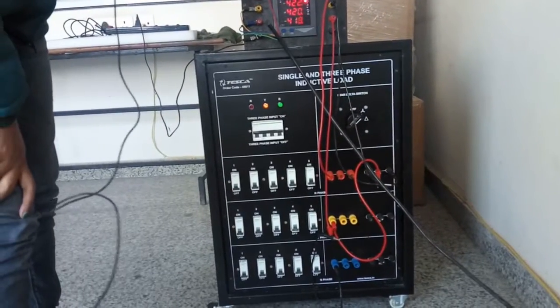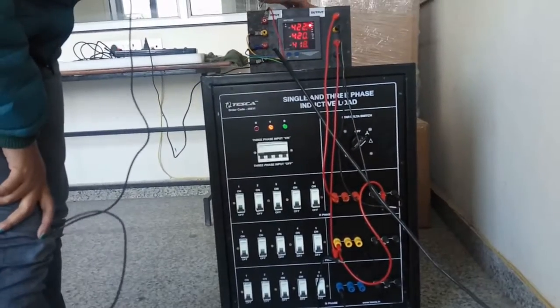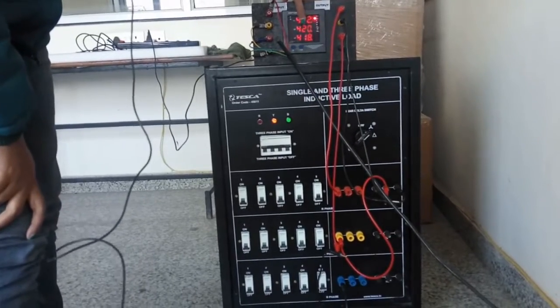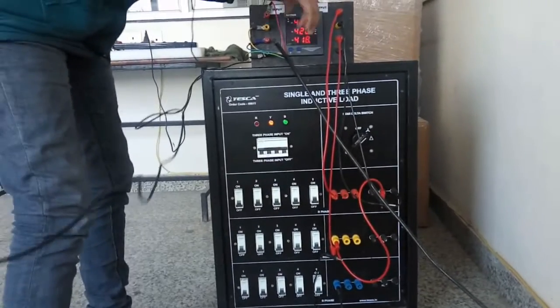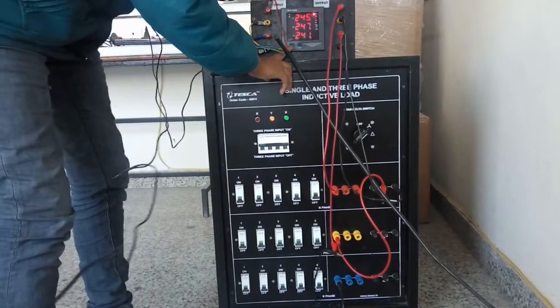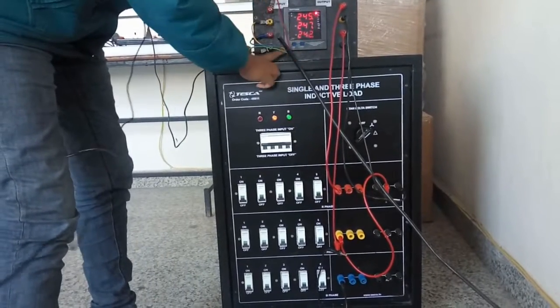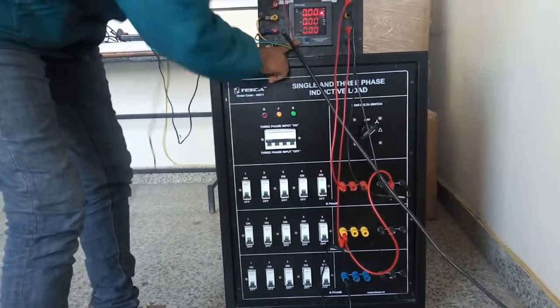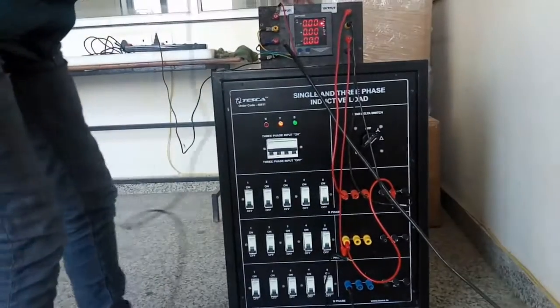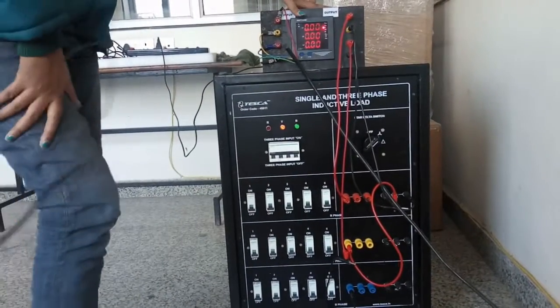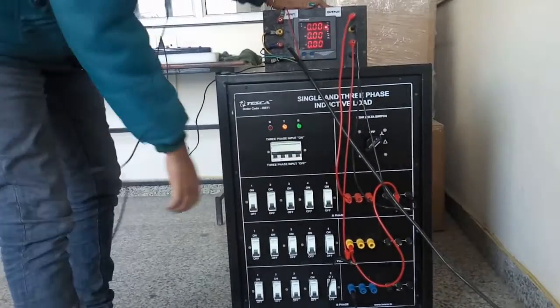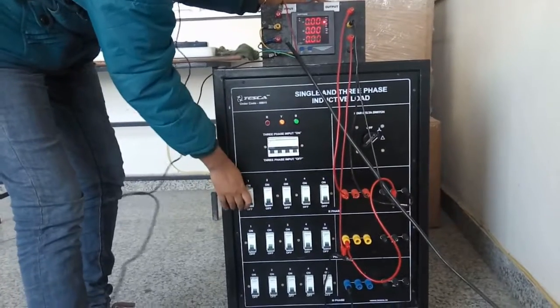Here we have the multi-functional meter. It is showing the line-to-line voltage: 422V, 424V, and 418V. This is a three-phase connection. This is the line-to-neutral voltage for three phase. Now we will observe the current per phase, so turn off the MCBs one by one.